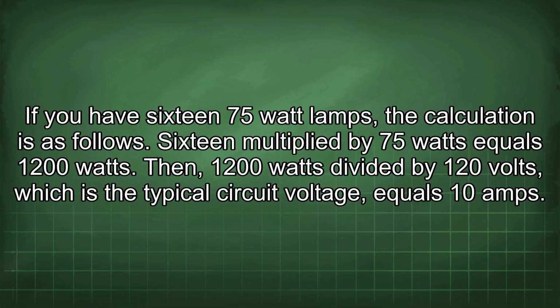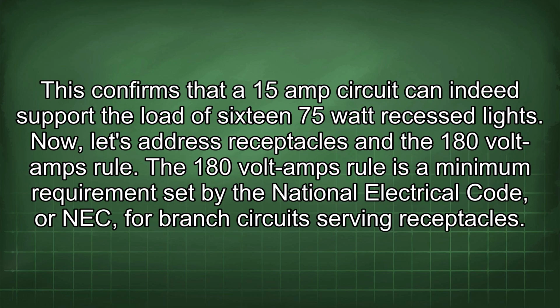16 multiplied by 75 watts equals 1200 watts. Then 1200 watts divided by 120 volts, which is the typical circuit voltage, equals 10 amps. This confirms that a 15 amp circuit can indeed support the load of 16 75 watt recessed lights. Now let's address receptacles and the 180 volt amps rule.